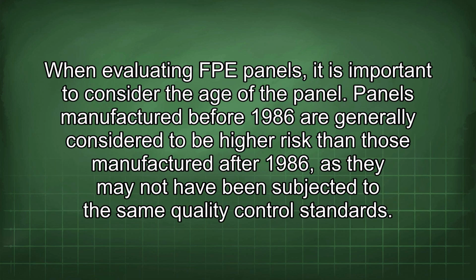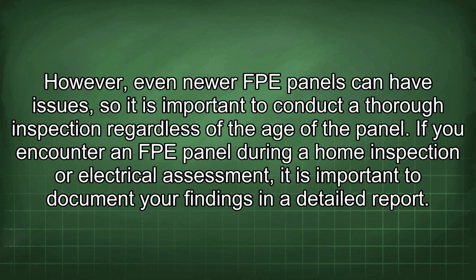When evaluating FPE panels, it is important to consider the age of the panel. Panels manufactured before 1986 are generally considered to be higher risk than those manufactured after 1986, as they may not have been subjected to the same quality control standards. However, even newer FPE panels can have issues, so it is important to conduct a thorough inspection regardless of the age of the panel.